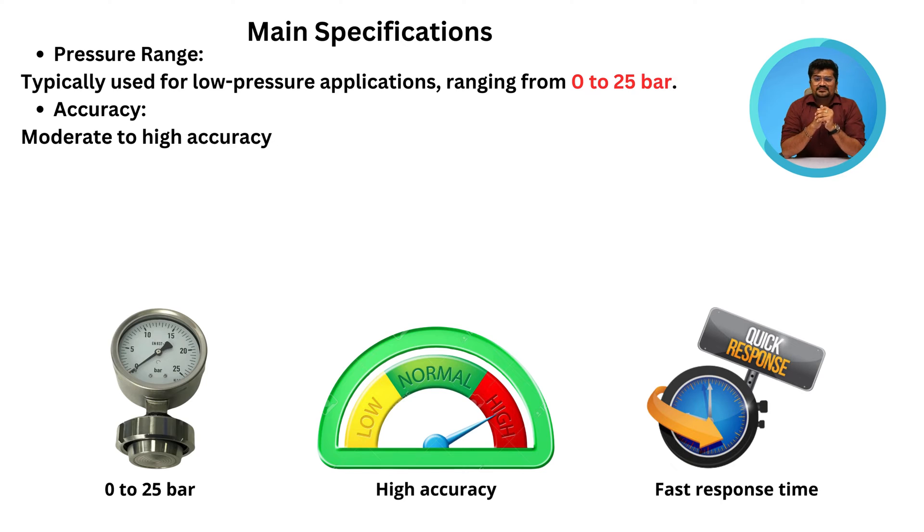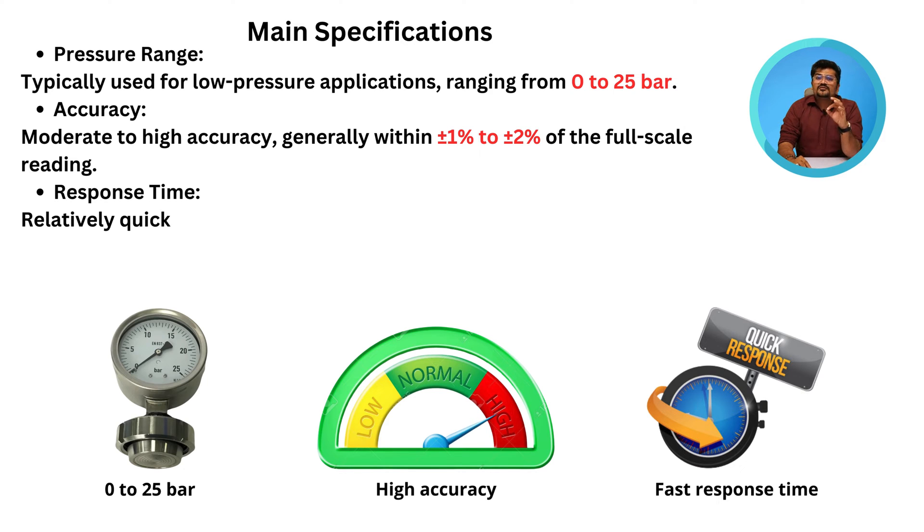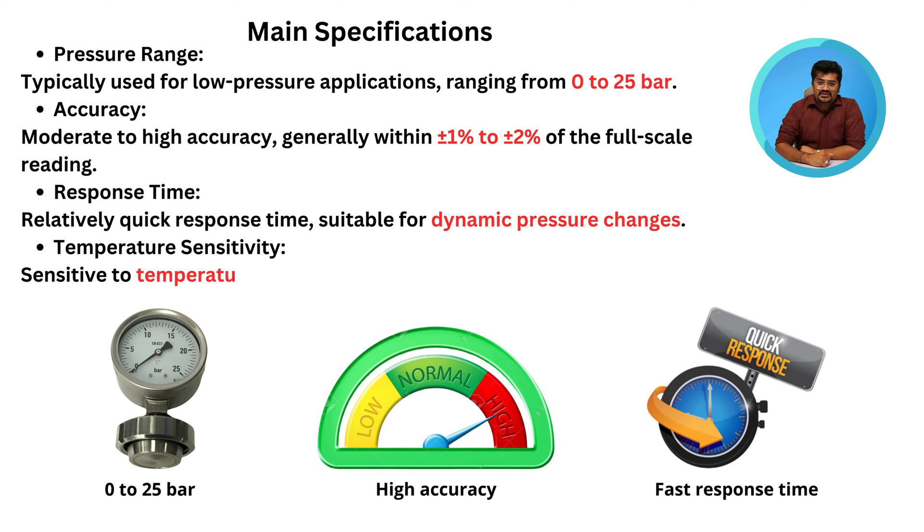Accuracy is moderate to high, generally within ±1% to ±2% of full span reading. Response time is fast, making it suitable for dynamic pressure measurements, though temperature sensitivity can affect accuracy.